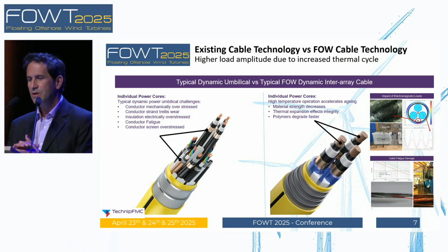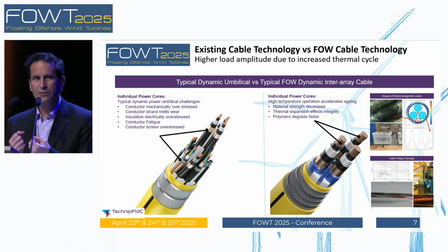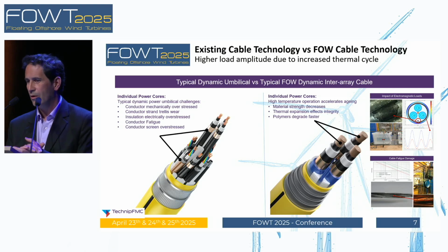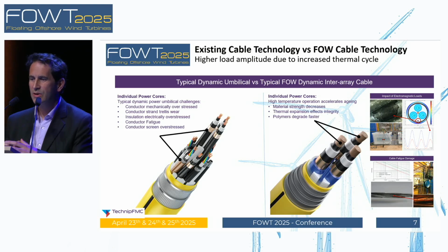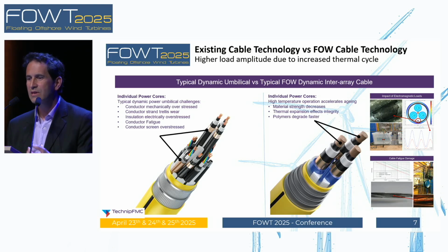So again, just like when you're installing, there are different areas where cyclic bending could be applied, and this cyclic bending is combined with high temperature, right? And if for some reason you compress too much, at any stage, this white layer that you see, the insulation, then it will create higher stress in the whole system. It could create asymmetrical heating, and then in the end you start to heat the different layers of the bundle again. You have the illustration here on the right-hand side. I won't say too much, but there is some electromagnetic effect here that could lead to some current in the carcass structure of the bundle, and therefore some heat generated and premature aging.